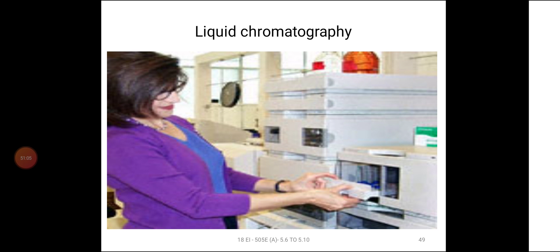The liquid chromatography block diagram consists of a mobile phase supply system that is connected to the pump and programmer. The next block is the pump and programmer and sample valve. The sample valve is connected to the column and thermostat. The column exit is connected to the detector. The detector converts these non-electrical signals into electrical signals, which are directly fed to the recorder, which records the amplitude versus the time function, called the liquid chromatogram. The detector outputs are also connected to the data acquisition system and programming and processing.